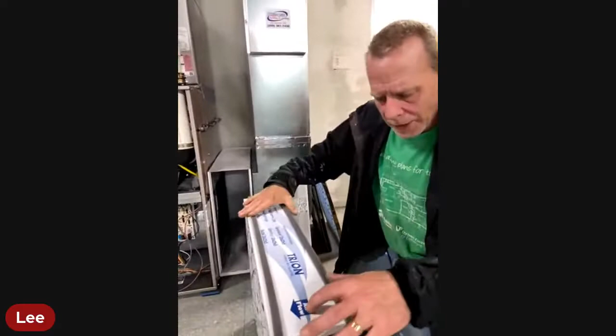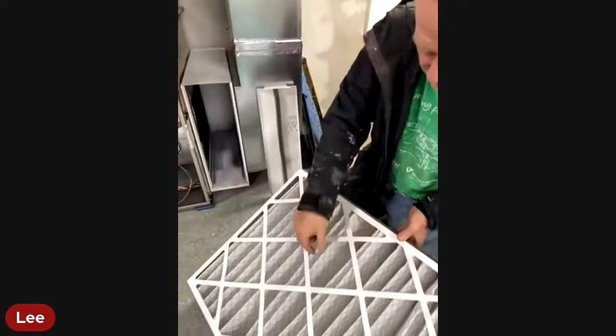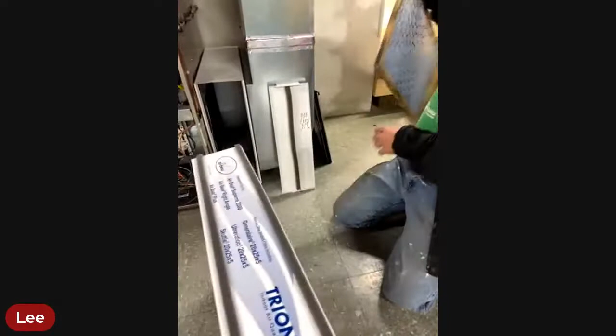The other thing is this little arrow, and that's important. Why? Well, I'll show you both sides. This side goes on the return air side, versus this side, which has kind of a metal mesh, and you'll see that on most furnaces. I don't care if one looks like this or like this, they're all going to have arrows. There's the arrow right there, and there's that arrow right there. That arrow always points towards the furnace, or in the direction of the airflow.